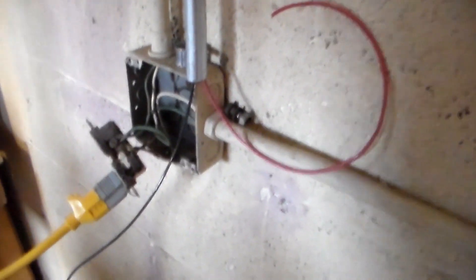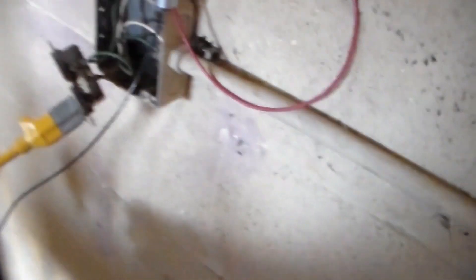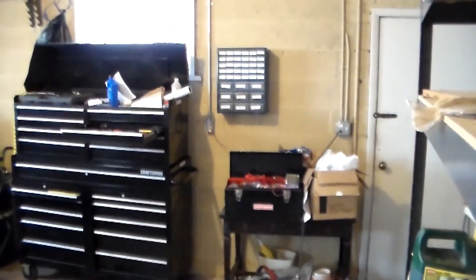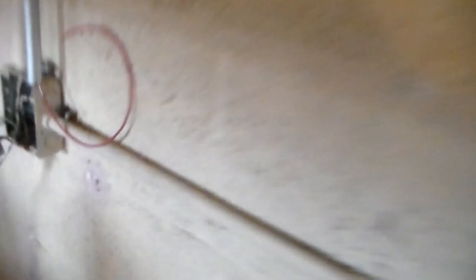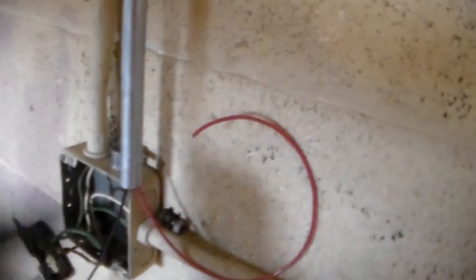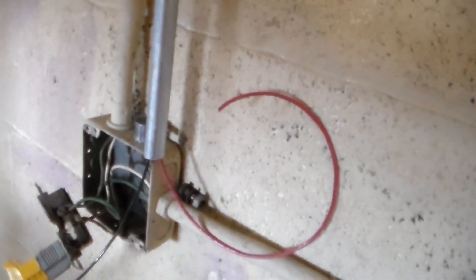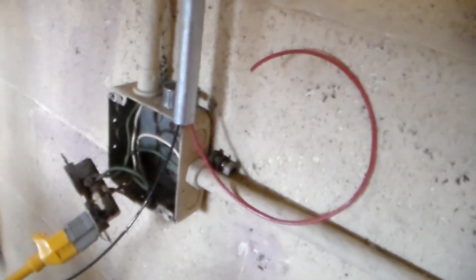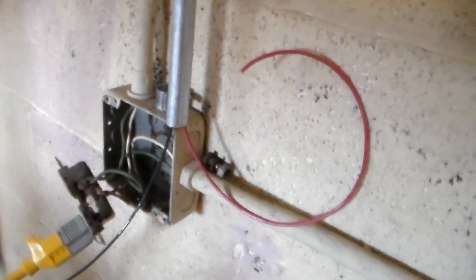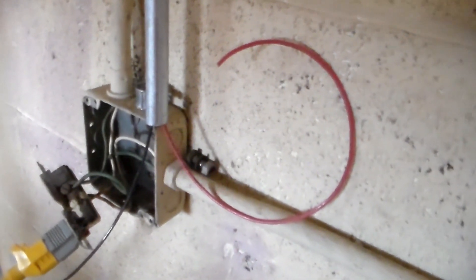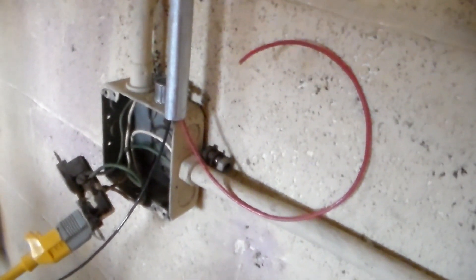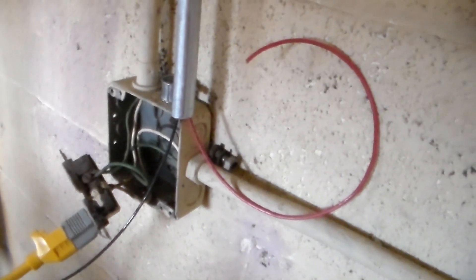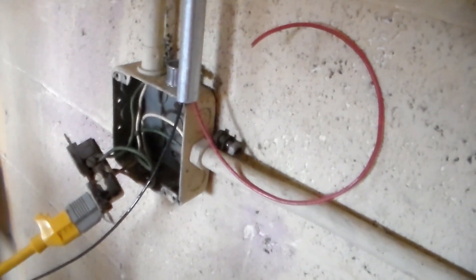Now when you cut your wires at the end of the conduit, you always want to have, I've got about 10 inches of wire here, both of them, which is good. And then on the other side, you see I got a good eight to 10 inches of wire there. You always want to have extra because if you cut yourself short, you cannot put connectors on these wires. Unlike car wiring, you cannot put connectors on this and have it inside this conduit here because it'll come loose and then you risk blowing fuses as well as setting the house on fire when you do haphazard work like that. So it's totally unacceptable and totally against the national electric code. So you always want to give yourself extra wire to work with.